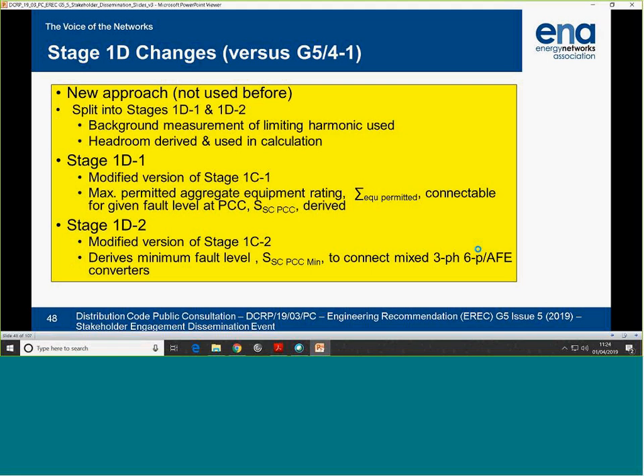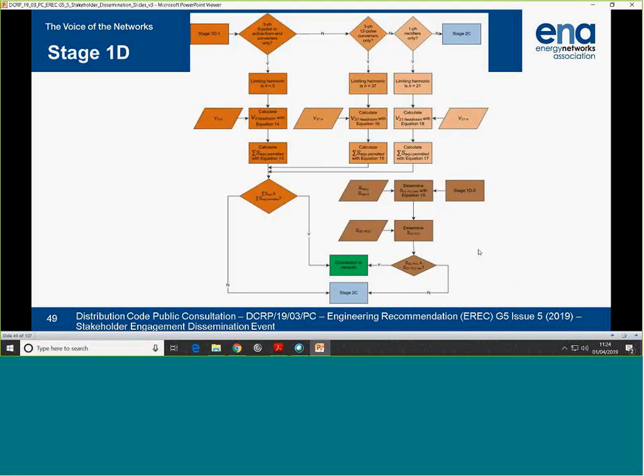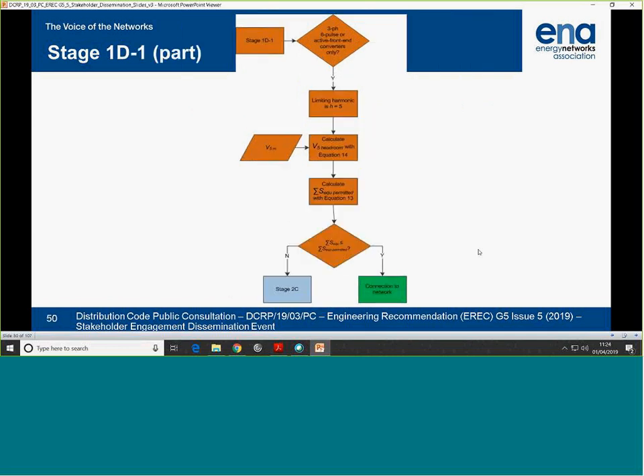So 1D is a more advanced version of 1C, where you are looking at the background voltage distortion as well. It'd be easy to just go straight on, avoid the words. The flowchart, you can't see it all there, but basically, there are branches looking at the different technology types. Each one is represented, and we'll just look at an extract of one of those. Again, you can't see the top on the screen there. So you've got, is it 6 pulse or active front end converter? Then it's the limiting harmonic, that's what we've worked out in terms of manipulation. Then we have an input of the background voltage distortion for the fifth.